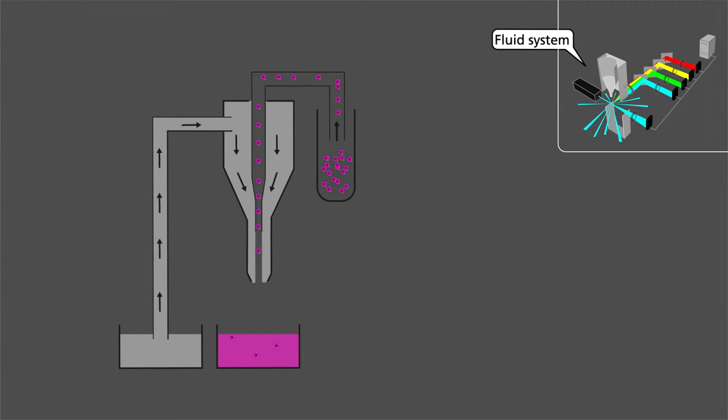In the cytometer, there is a circulating flow of liquid called sheath passing in front of the laser. The sample that we want to analyze is injected into the sheath of the cytometer.